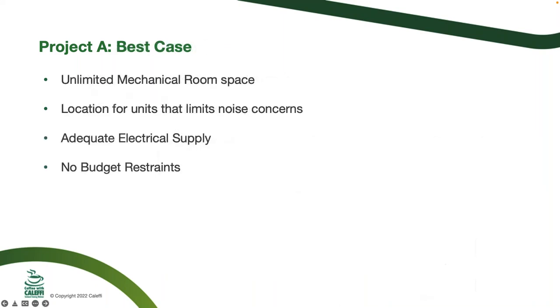Since it's San Francisco and a relatively fair climate, the best scenario is probably to put the heat pumps and tanks outdoors. That saves valuable footprint inside the building and gives you more leeway on noise levels — a really important consideration. These heat pump systems are going to be noticeably louder when operating than a traditional gas combustion water heater, with around 9,000 CFM of airflow from the fans plus the compressor making a big difference.